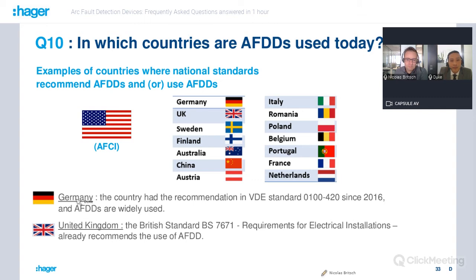If we take an example focused on Germany and the United Kingdom: Germany has had the recommendation in its national standard, the VDE 100, since 2016, and today AFDDs are widely used in Germany. They have a strong recommendation to use AFDD. In the United Kingdom, the British standard BS 7671 recommends the use of AFDD as well, and there are a lot of ongoing projects to push for a higher level of recommendation, or to make AFDDs mandatory in these standards.